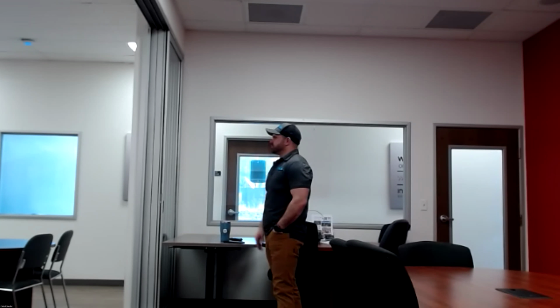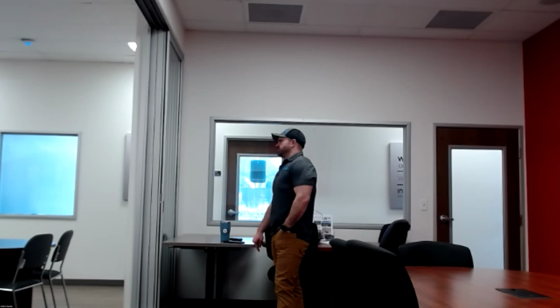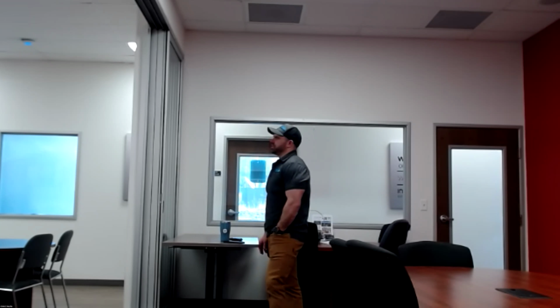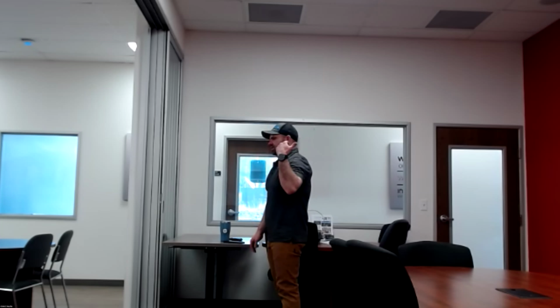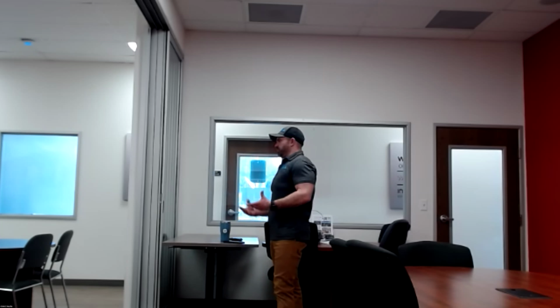What's the normal volume? In other words, is it continuous because it's coming from the boiler? Its recovery rate is going to be between an on-demand or tankless that you can run forever and never runs out, and a gas water heater. So they recover a lot faster than a tank water heater. In one of my personal buildings, I've got a triplex with 5 bathrooms and 3 laundry rooms. We have a 35-gallon sidearm water heater, and it keeps up with everything just fine. It's a super good unit, and they work really well.